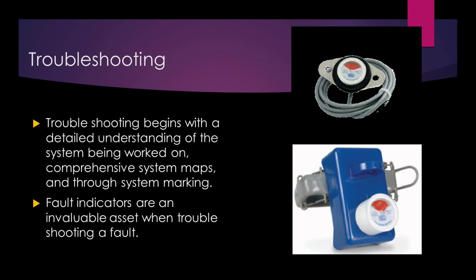So that somebody doesn't get confused, thinking the light flashing means it's hot, or the light not flashing means it's hot. Everybody needs to know this, and it helps cut down on troubleshooting time. For some of the smaller places, you go to the center of it. If you've got a radial tap, you go about halfway down, pull an elbow, put it on a parking stand, and close the fuse in. If it blows, it's in that direction, back toward the fuse. If it doesn't blow, it's on the other side of that elbow. That's a lot of troubleshooting right there.